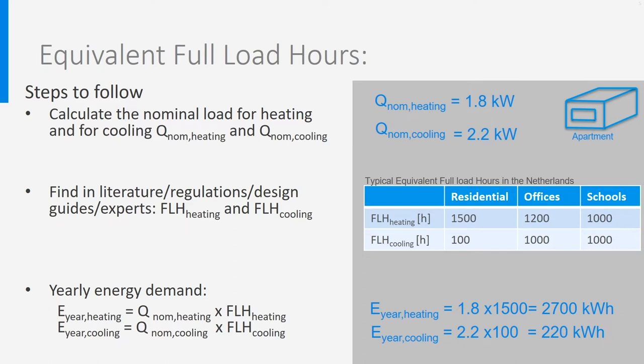The second step is to look in the literature, norms, or guides for estimations of the full load hours. For instance, in the Netherlands for a residential building, the full load hours for heating are around 1500, while there are only 100 for cooling. The last step is to multiply the nominal power by the full load hours, which gives an annual energy demand for space heating of 2700 kilowatt-hours, and for the cooling it is 220 kilowatt-hours.